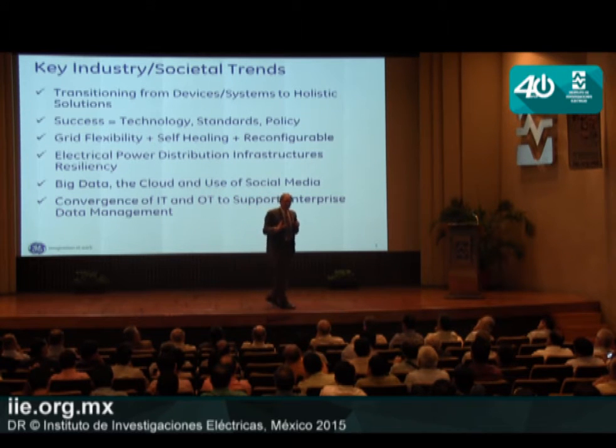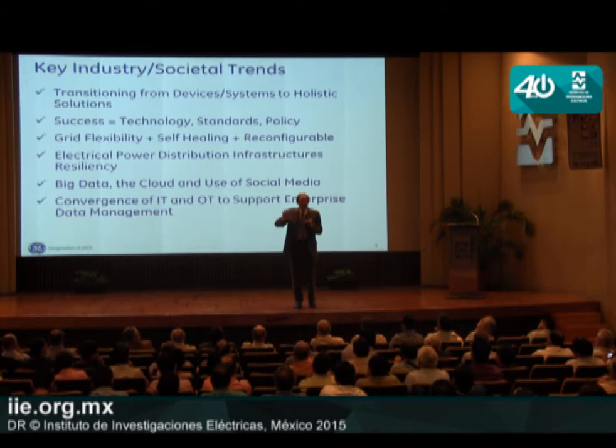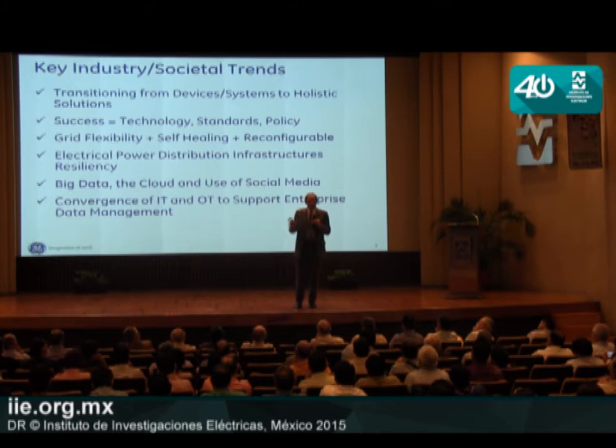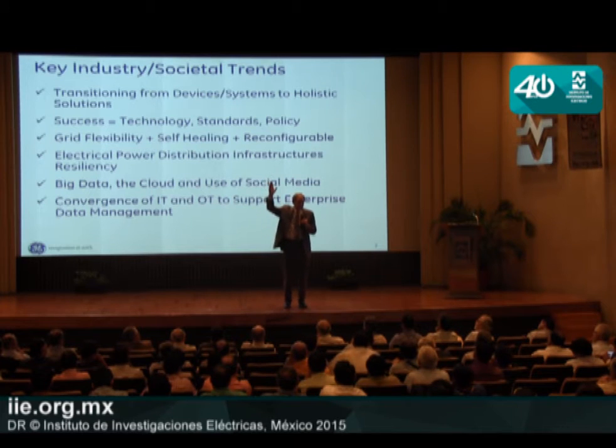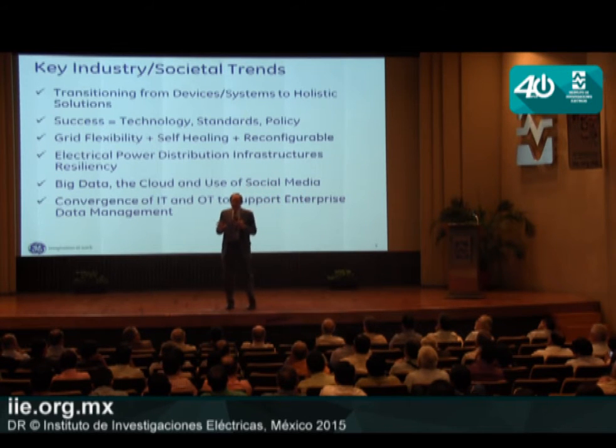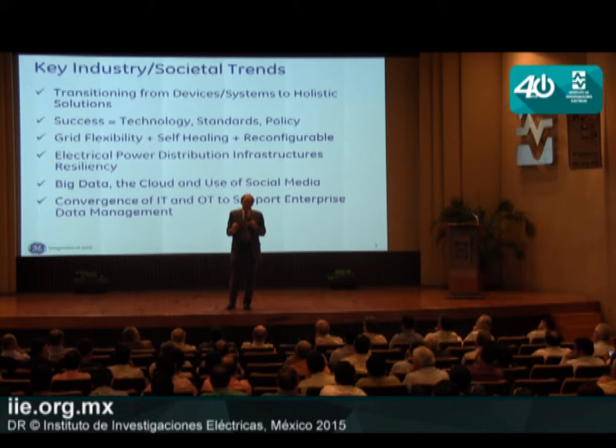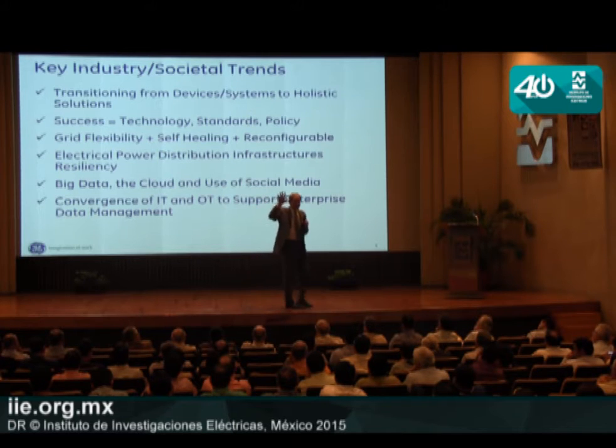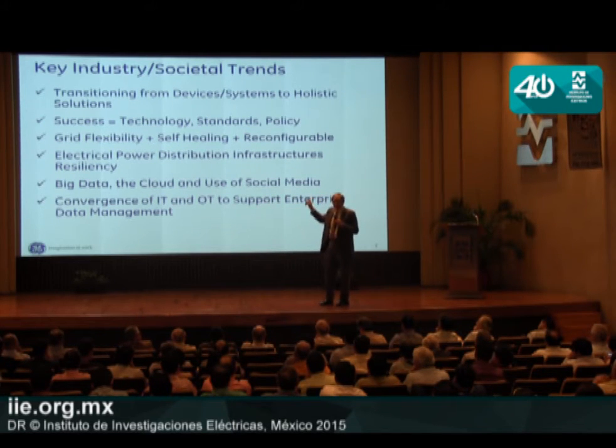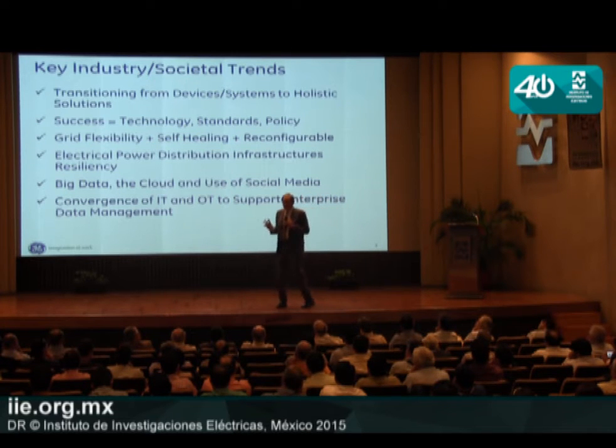What we're doing now is distributing intelligence downstream. We can run a number of applications at the substation level that analyze the data, make decisions, execute them, and report upstream afterward. This puts a lot less burden on the control center. So the ultimate architecture today isn't centralized, but a hybrid, a combination of centralized and distributed. The second part of self-healing, once we distribute the logic, is to close the loop on it, especially on the distribution system.